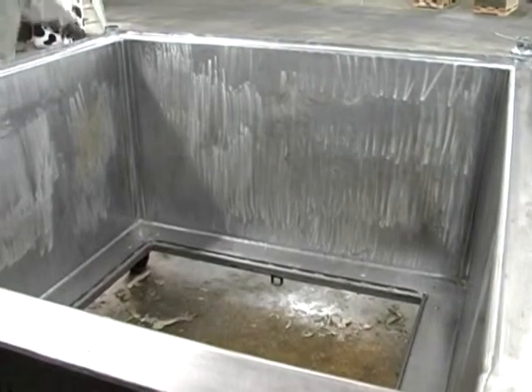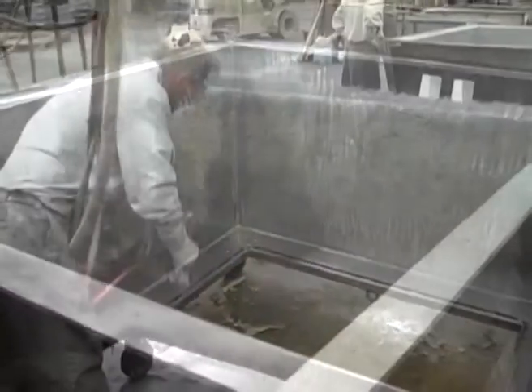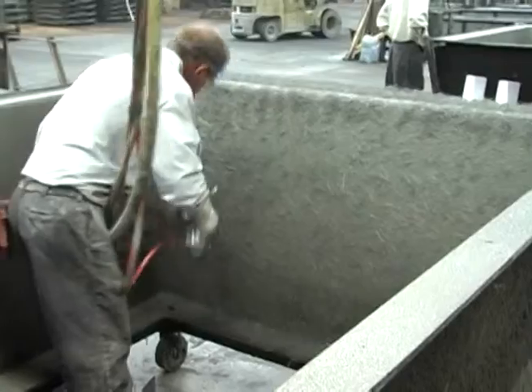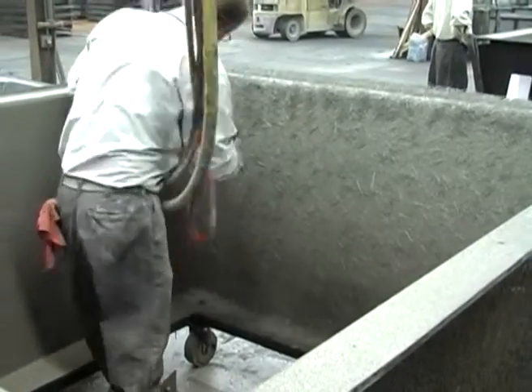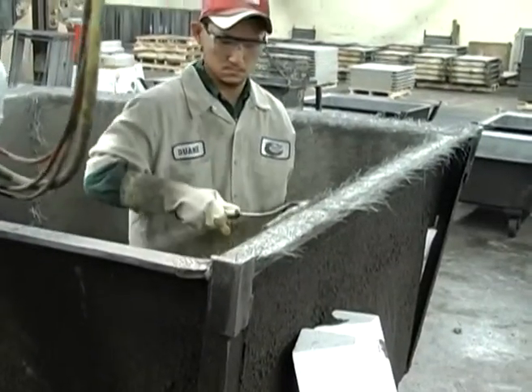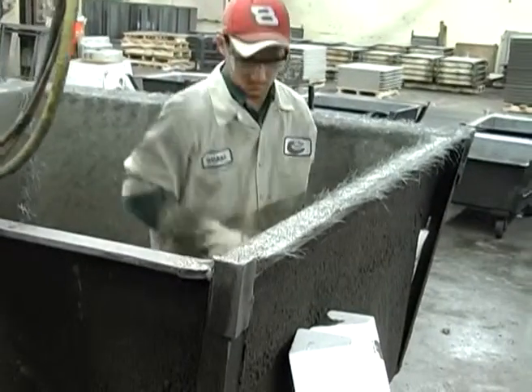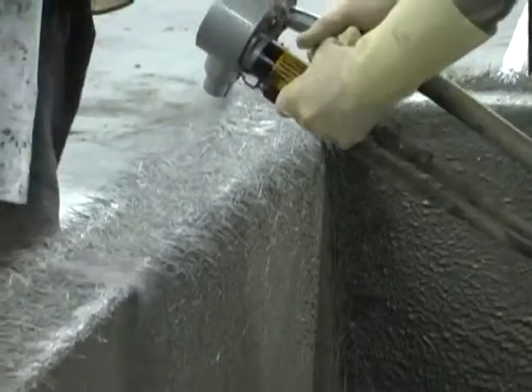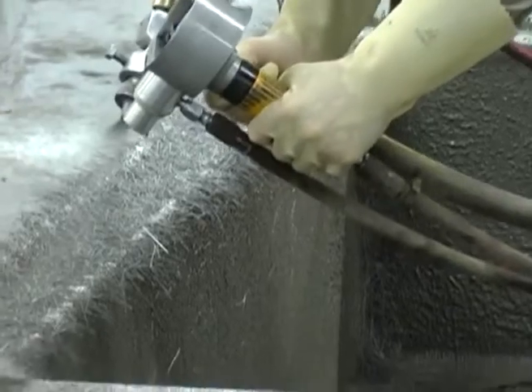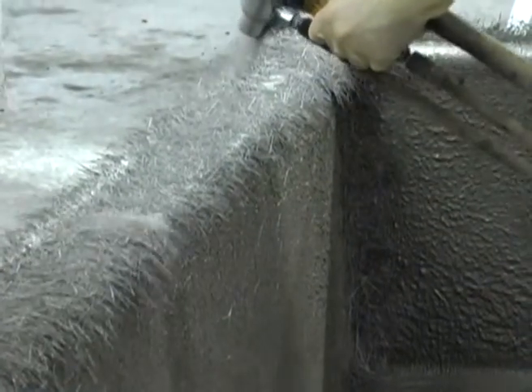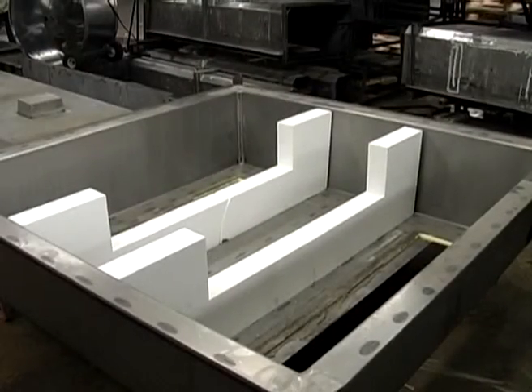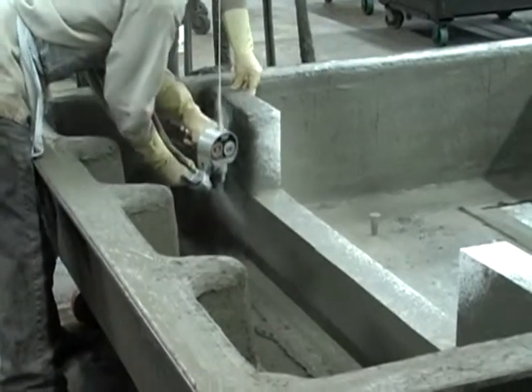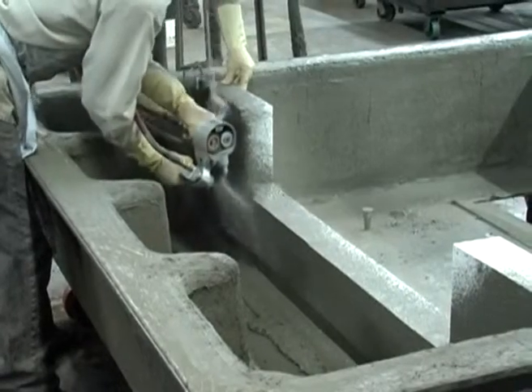Box pads are manufactured with a spray-up process over a steel mold. As the concrete slurry is sprayed onto the mold, alkali-resistant glass fibers are chopped and integrated into the matrix. Multiple layers are required to build to the designed wall thickness. Structural formers and high-strength steel wire are added when additional strength is needed in the walls, corners, or the top.